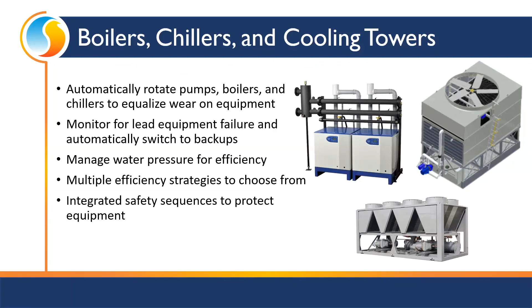Okay, we do have integrated safety sequences to protect equipment. If you're dealing with water-cooled chillers, you know, that's dependent on other equipment that the chiller doesn't have control over. If that water starts coming in too hot because something else has failed, we can shut things down or stage things back just to protect the very expensive equipment so we don't do damage.